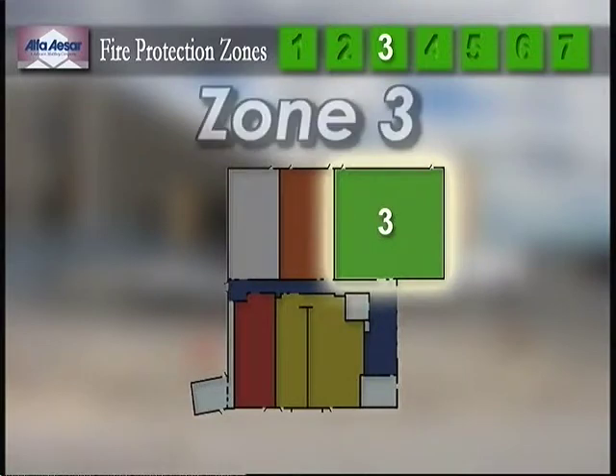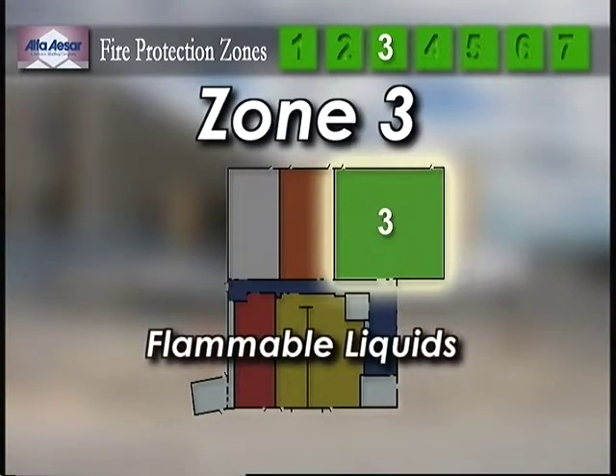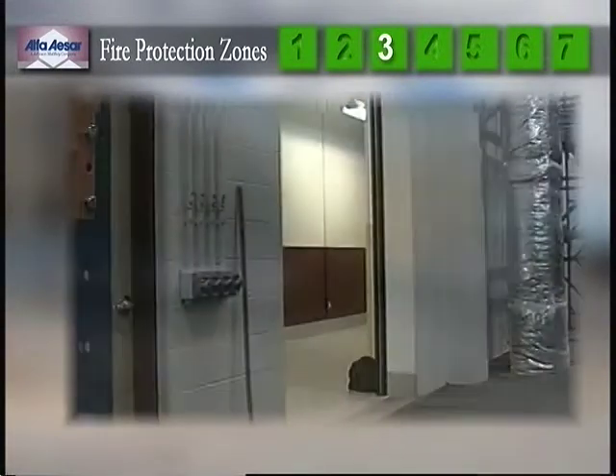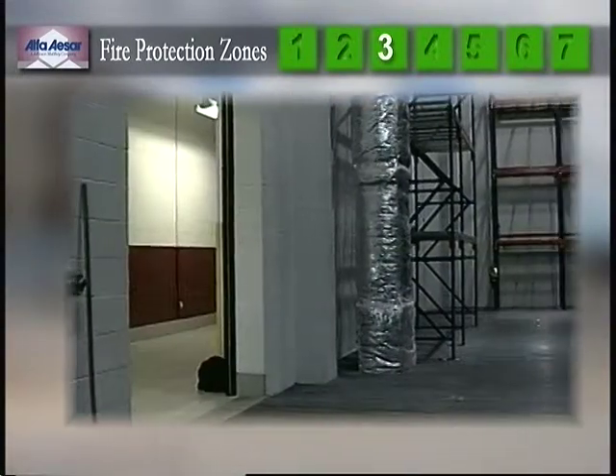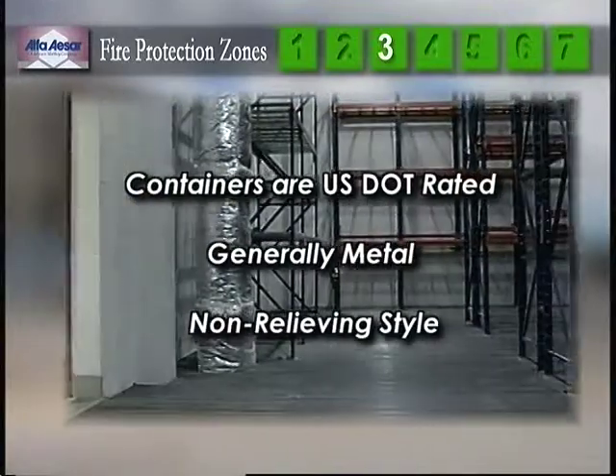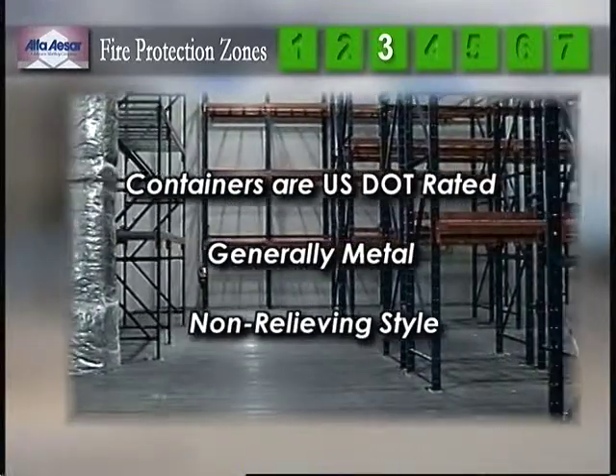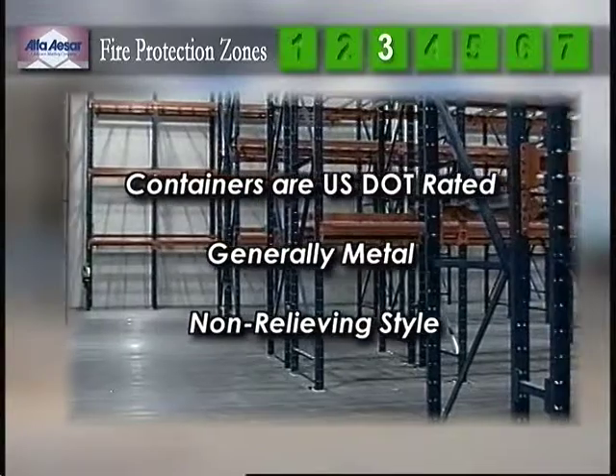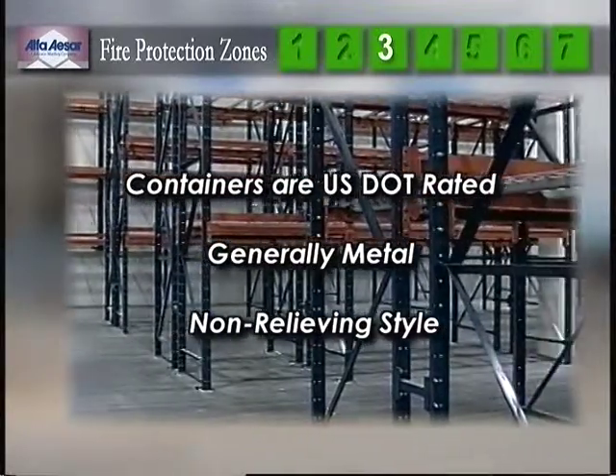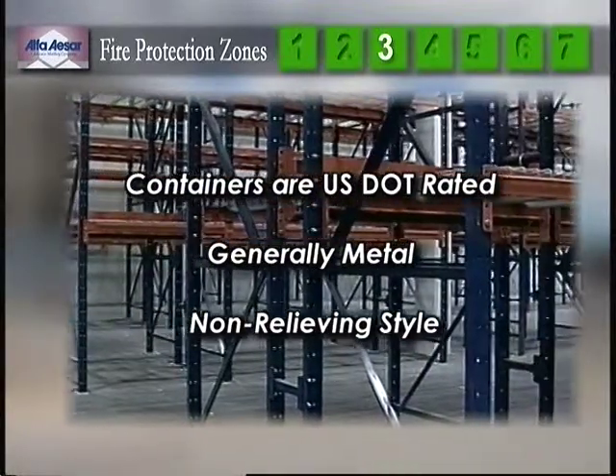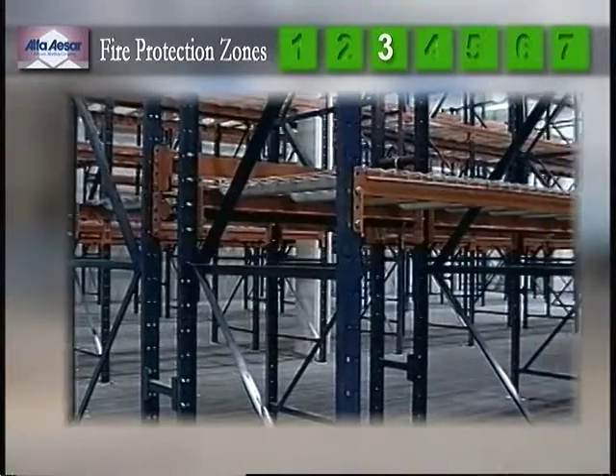Zone 3 is the largest storage space in the warehouse. This 8,900 square foot area is where the flammable liquids are stored, including materials classified as 1B and 1C flammable liquids. Containers are primarily U.S. Department of Transportation rated and approved to contain the product. They are generally metal, although some containers are plastic. All of the containers are non-relieving style containers, consistent with the limitations and requirements.